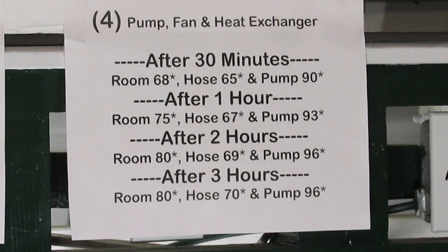What can we learn from test number 4? By using both the fan and heat exchanger, the hose temp is kept below the room temp. In fact, at no point in time did the hose temp rise above the room temp, and at one point was 11 degrees cooler. The results of these tests I consider a success.